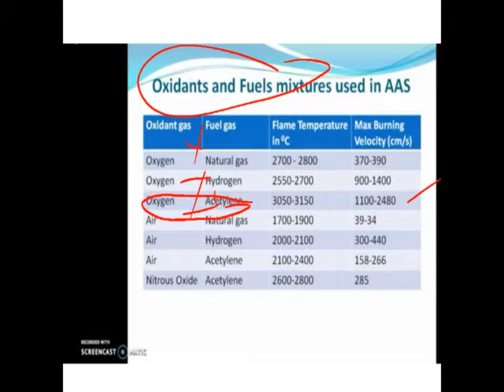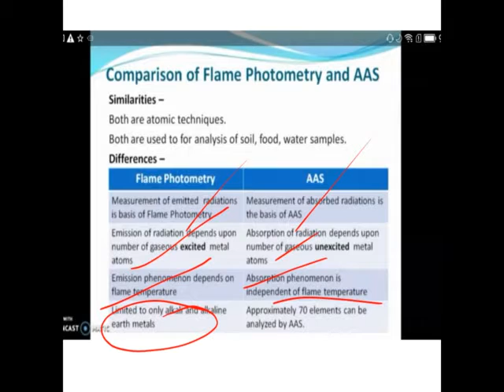So this is the comparison with flame photometry. In emission, the emitted radiations are measured. In absorption spectroscopy, the absorbed radiations are measured. In emission, the excited metal atoms are studied. In absorption, the unexcited or ground state metal atoms are studied. The emission phenomenon is based on flame temperature, while the absorption phenomenon is independent of flame temperature. Flame photometry is limited to alkali and alkaline earth metals, while atomic absorption spectroscopy is useful for determining more than 70 elements.